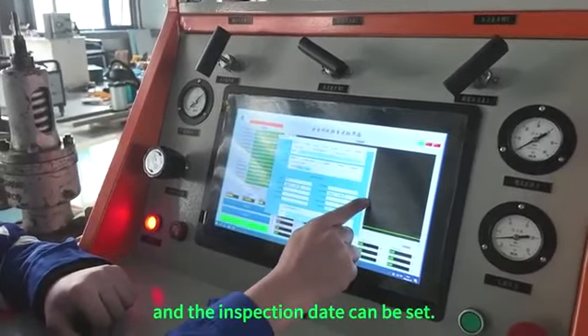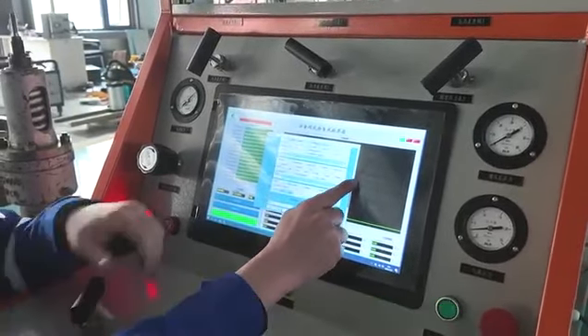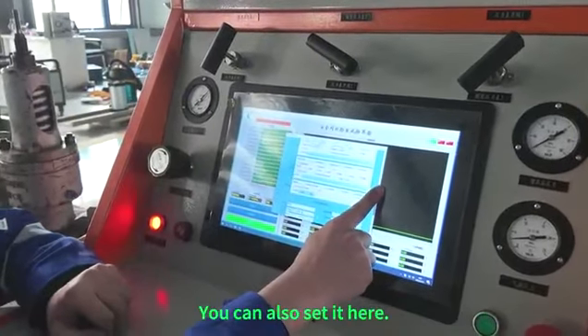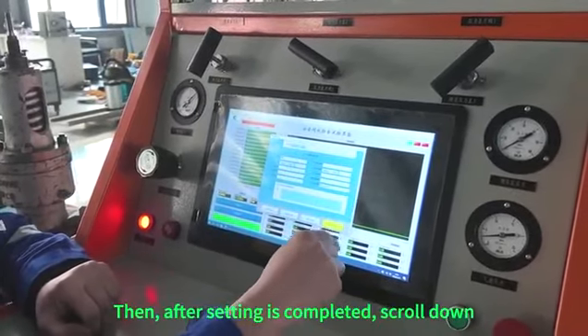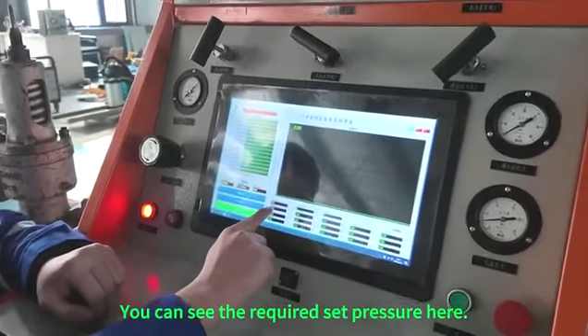The recipient, the client, and the inspection date can be set. Then you can do appearance inspection, disassembly inspection, and unqualified items. You can also set them here. After setting is completed, scroll down and click this to confirm the input. You can see the required set pressure here, which is 1.44 megapascals.